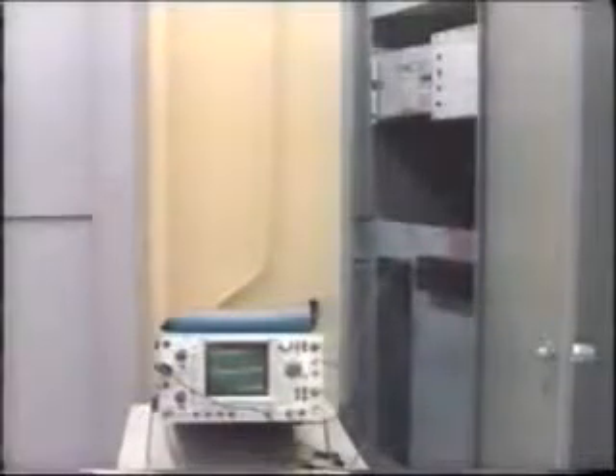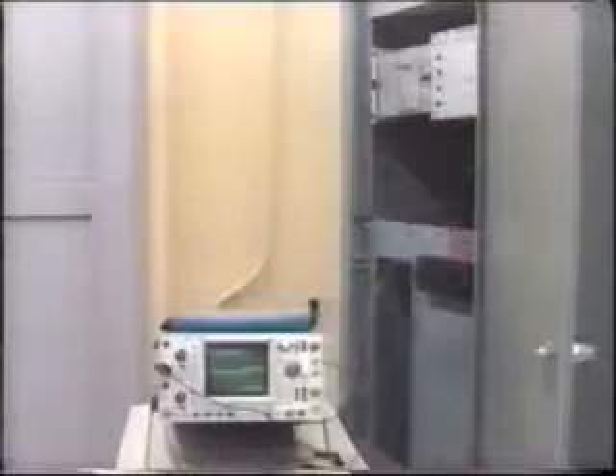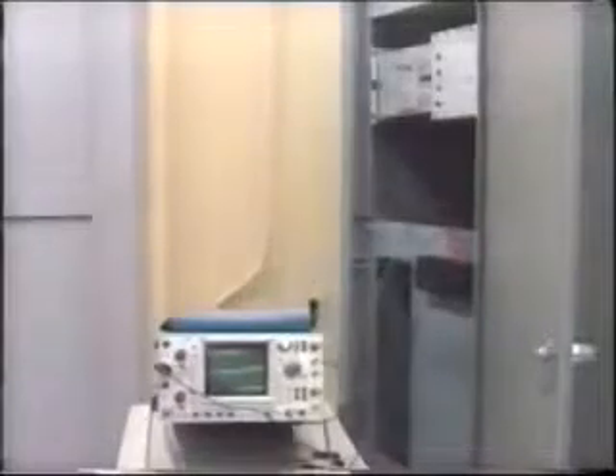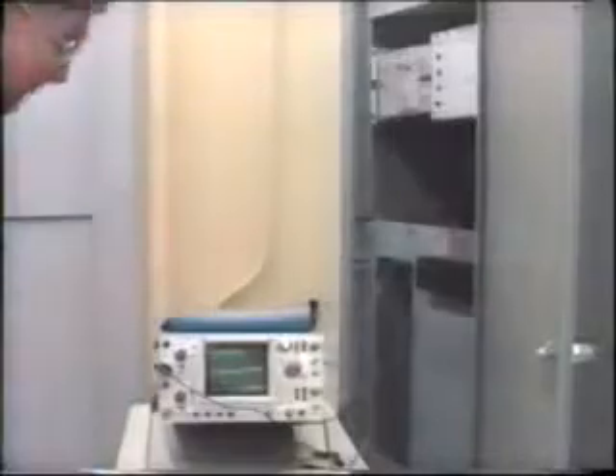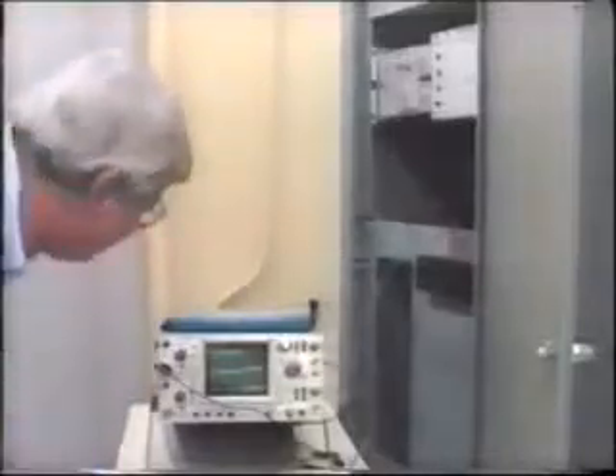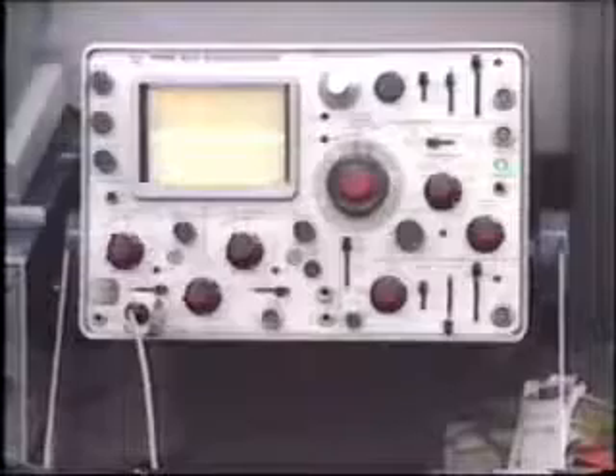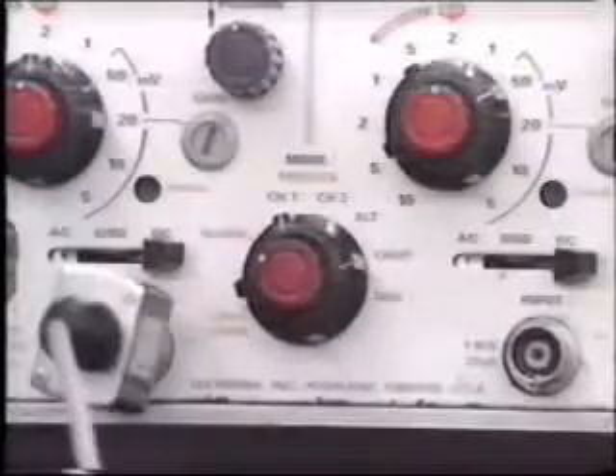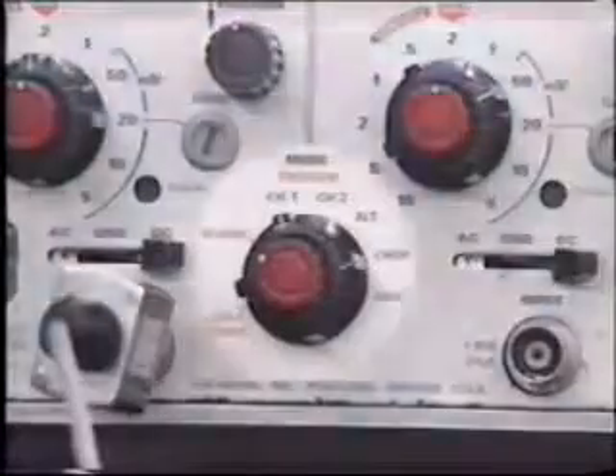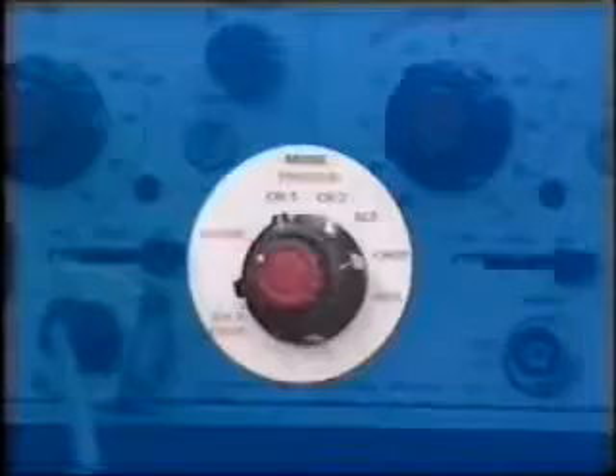The phase comparison relay also needs a propagation delay adjustment to delay the local CT signal to exactly match the CT signal from the line's remote end. Here is where a 2-channel scope enters the arena. Let us look again at the scope's vertical input section. We see a display selector switch for channel 1, channel 2, CHOP, and ALT. We have been using channel 1 only until now.